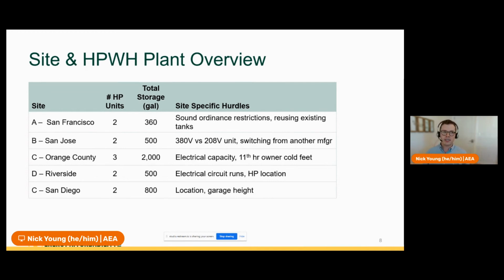But in existing buildings, and we've got a lot of existing buildings that we need to retrofit over the next, not very long, you may not have space for that really large storage tank. So what are the trade-offs, and how little storage could you reasonably have and still have a relatively efficient system? Or how many more heat pumps would you need to make up for that small storage? And how would that system respond to demand events? And could you still do load shifting if you had enough heat pumps but not too much storage, and things like that? We had some site-specific hurdles for each of these.